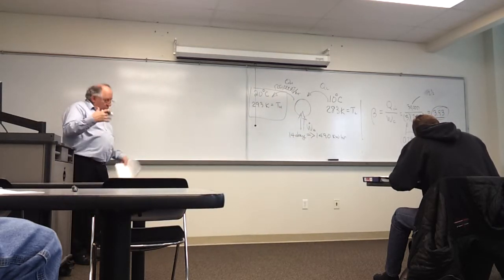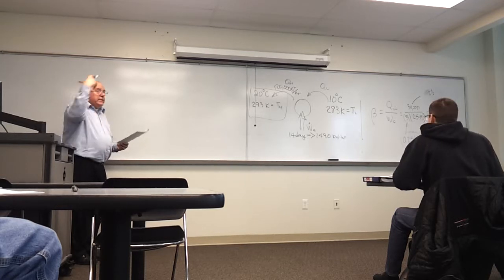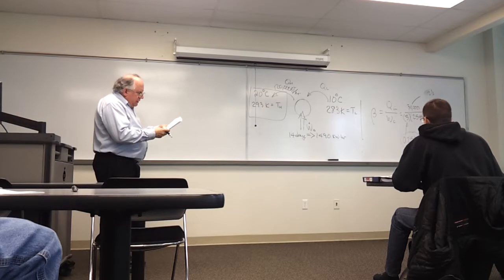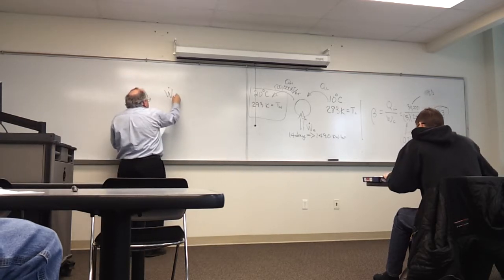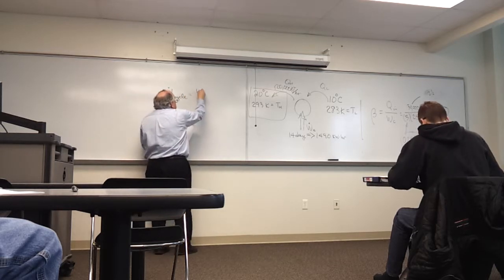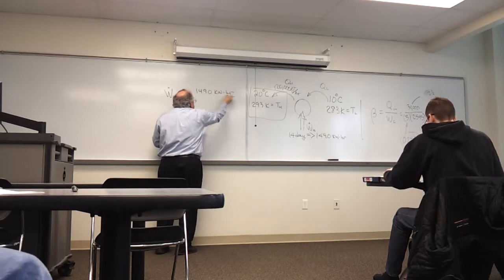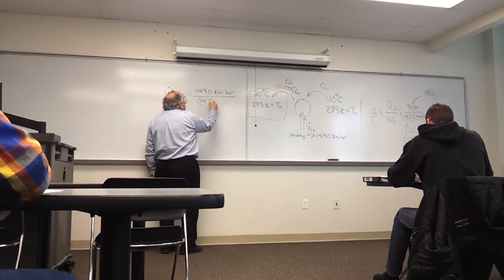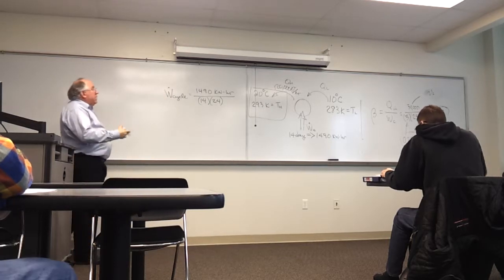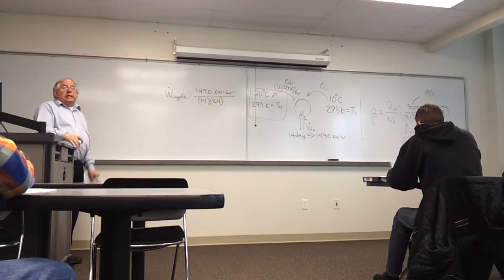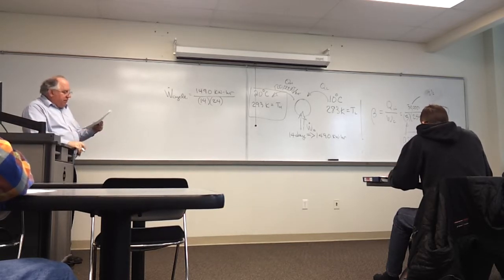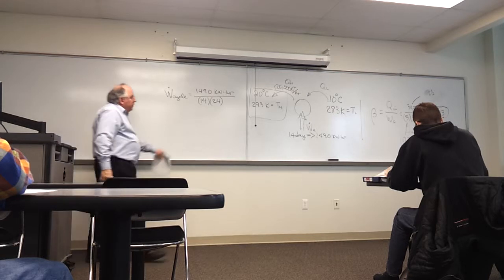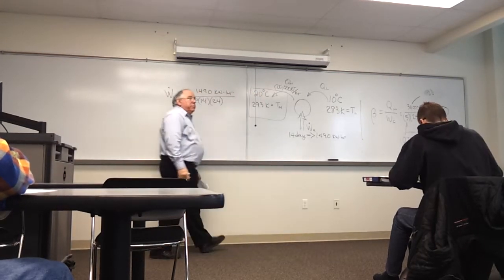Okay? And we're going to make the assumption that this system is running continuously. So making the assumption that it's running continuously, what can we say about the work rate of the cycle? We know that we're using 1490 kilowatt hours of energy, and how many hours did we run? 14 days times 24. And so by dividing the number of hours into our usage in kilowatt hours, this allows us to determine the kilowatt energy going in as the compressor power.